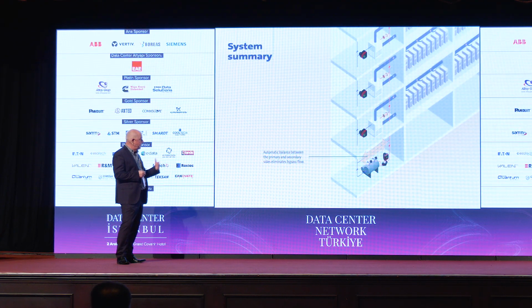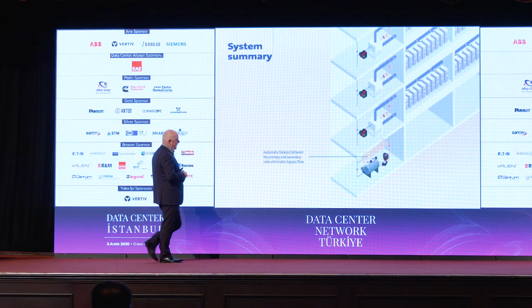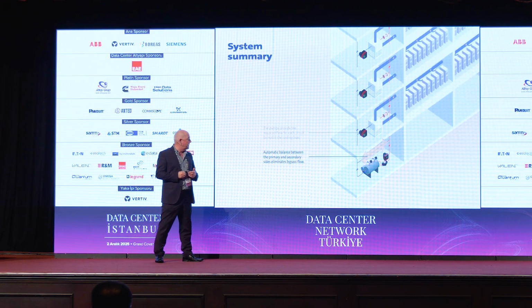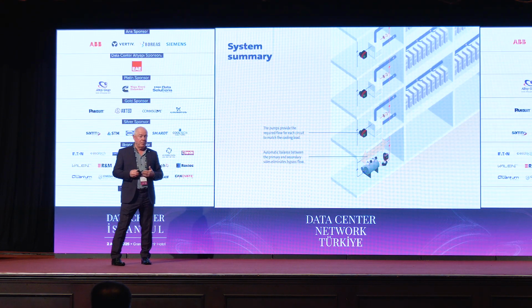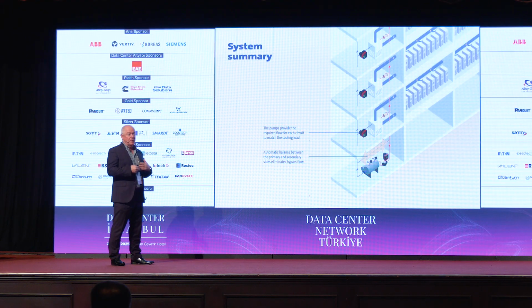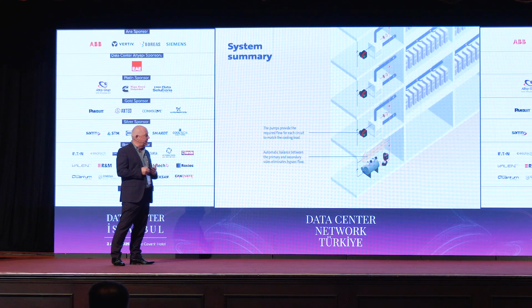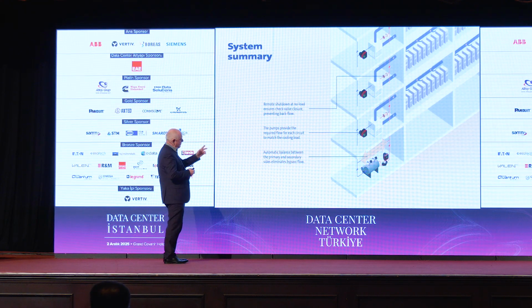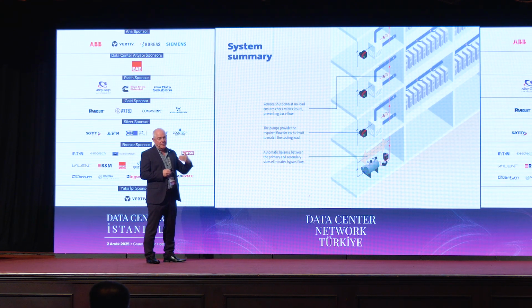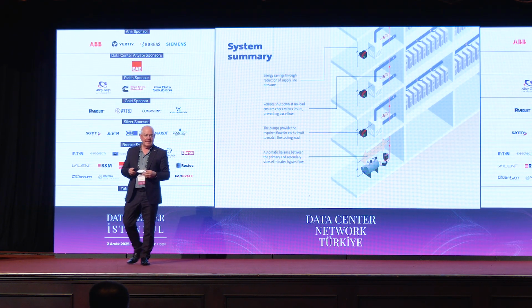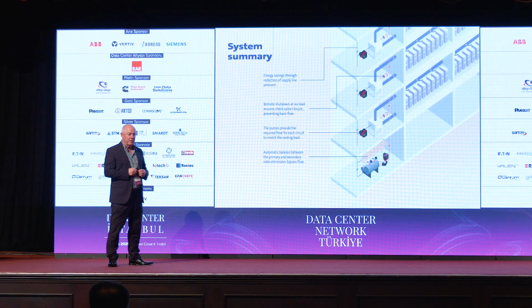So if we just recap, we balance the primary and secondary circuits. We use pumps instead of valves, so we don't need to generate as much pressure to overcome the resistance across a valve, and that's energy saving. We put non-return valves on the system so that we don't get backflow if parts of the system are switched off, and less friction in the system, less energy required to pump across it.